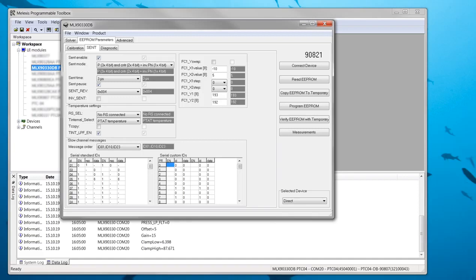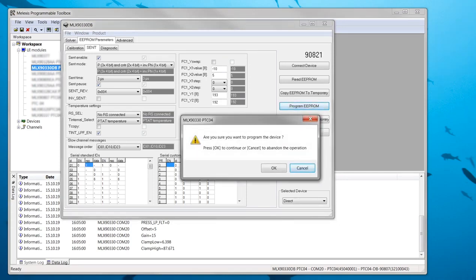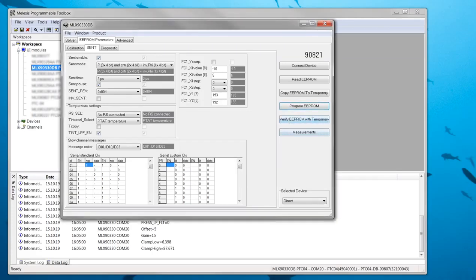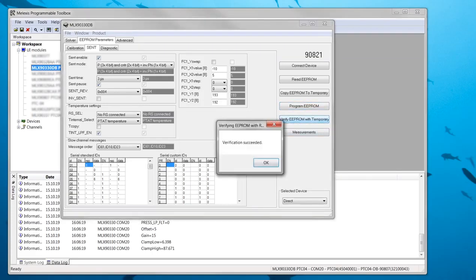The next step is to program the E²ROM and then verify that the new settings were written correctly by pressing the buttons Program E²ROM and Verify E²ROM with Temporary. Pressing the Program E²ROM button creates a pop-up window to confirm that you want to override the current E²ROM content. The Verify E²ROM with Temporary button also causes a pop-up to appear to show whether the programming was successful.